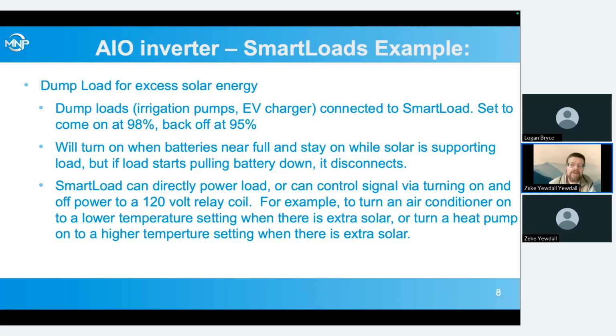And also, we usually don't want to wait all the way to 100% to come on, because there can be quite a delay between 98% and 100%, as it kind of does its very slow finish charge and recalibrates the BMS. So 98% will kick it on quite a bit sooner usually. And at that point, we really don't need much solar to be doing that top off of the batteries. So we might as well start dumping it into some of these dump loads.